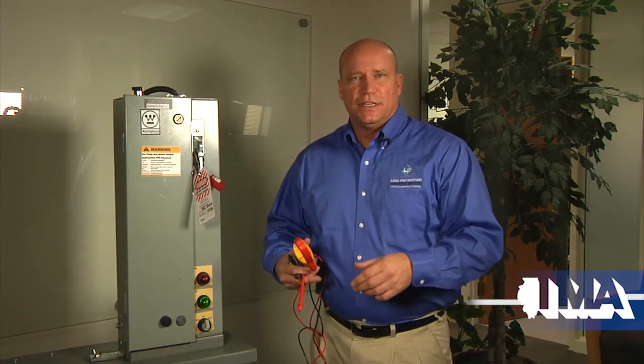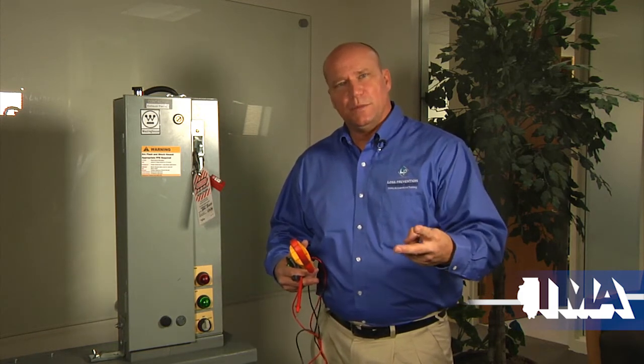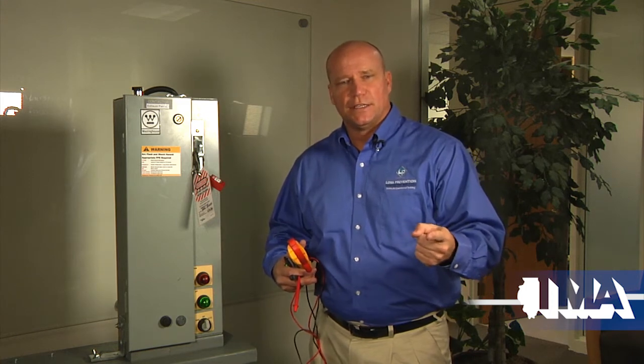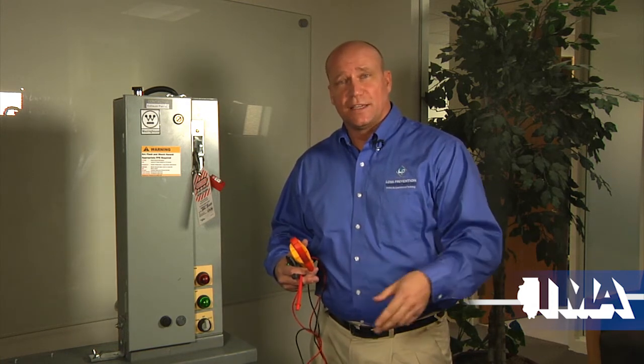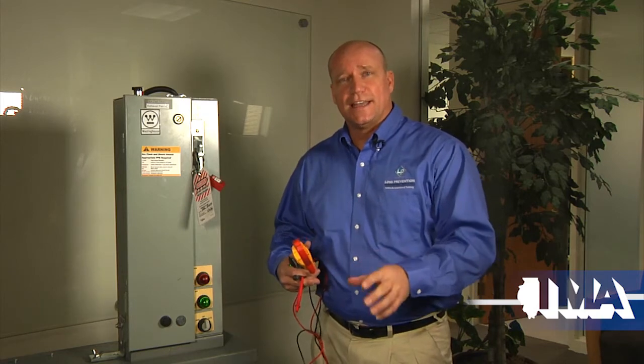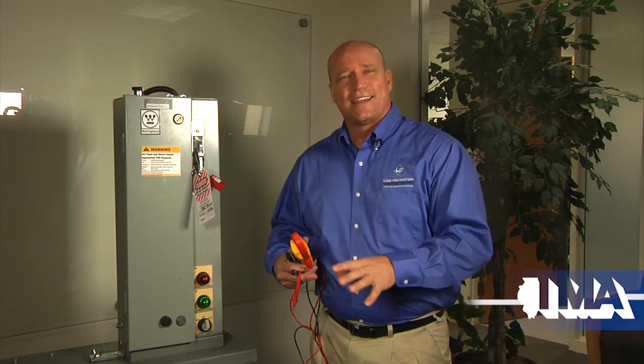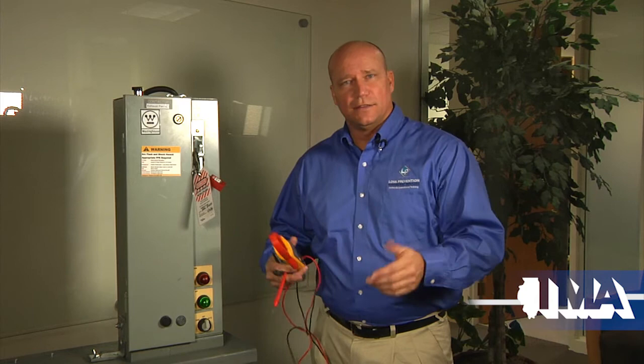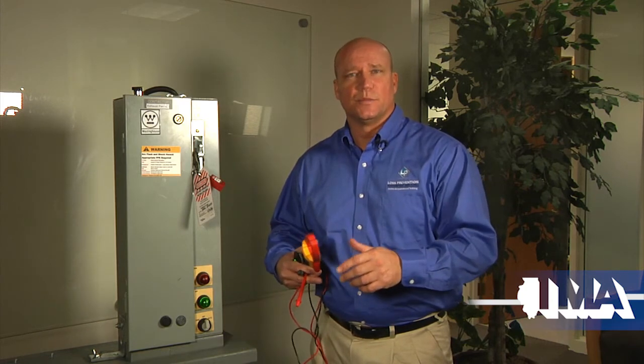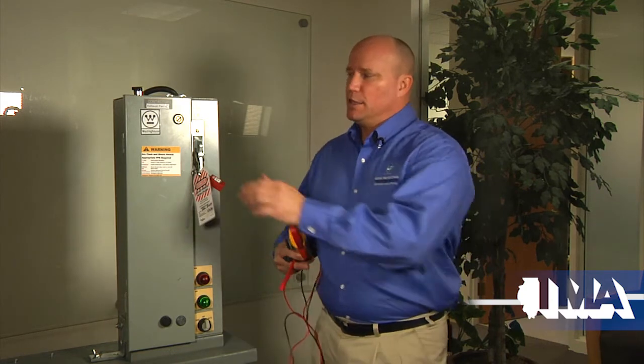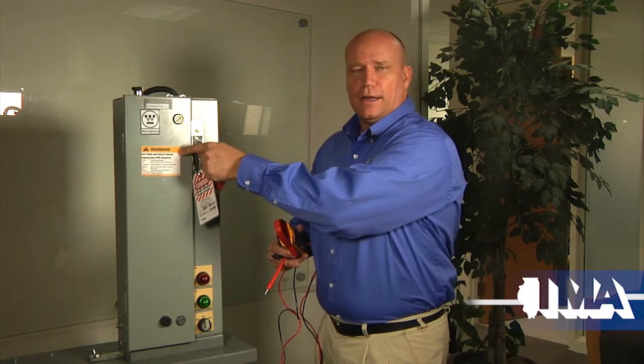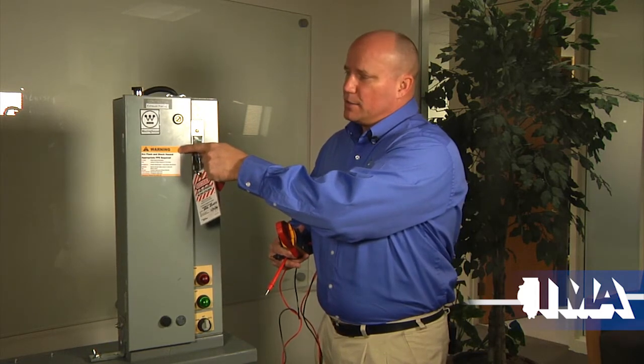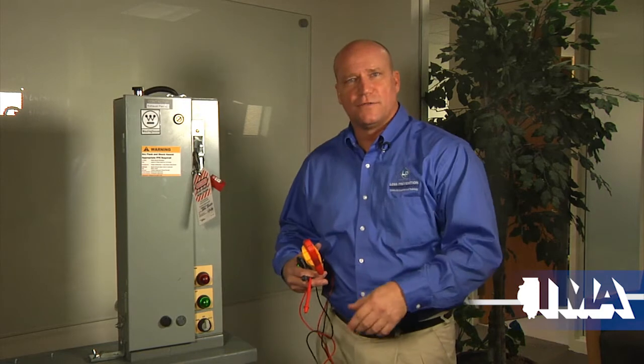so when you're doing hazardous equipment type work that you're protected. In NFPA 70E, there's two methods to select the level of PPE. One is using the incident energy analysis method. That can either be conducted using the annexes or the appendix in the back of the NFPA 70E and calculate those using the calculations in the appropriate section, but also can be used by or abided by looking at the arc flash labels if you had an arc flash analysis.